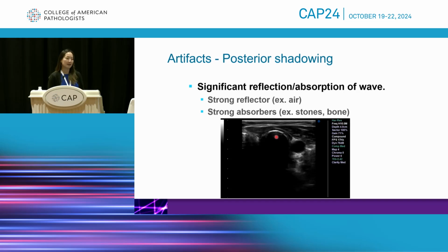This also means that if you're running an academic practice and your trainee doesn't put any gel between the probe and the probe cover, you're going to have a big air bubble, and you're not going to be able to see anything. So I have run into this many times where my trainee has sworn to me that they put gel on, and they didn't. And they're like, "There's something wrong with the machine, Dr. Jang." And I'm like, let's just take that probe cover off and put some gel on. Easy troubleshooting. I know, if only all our problems were so easily solved, right?